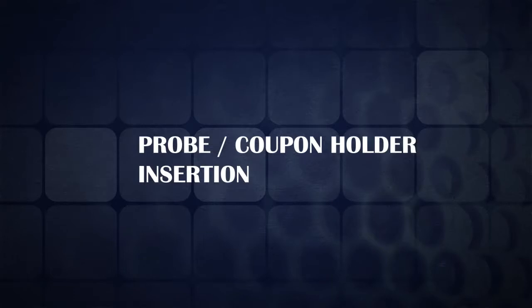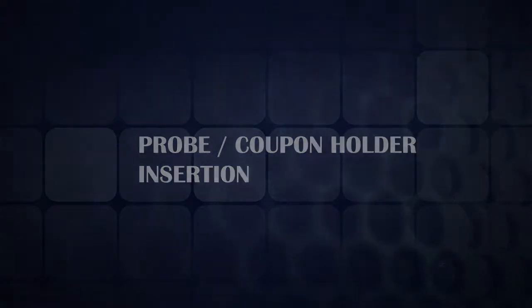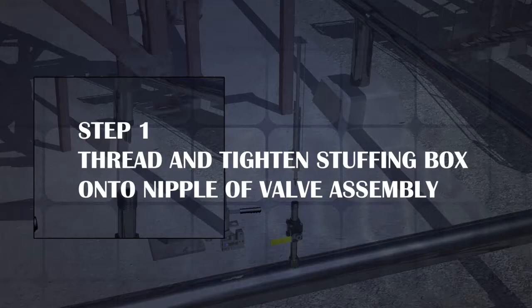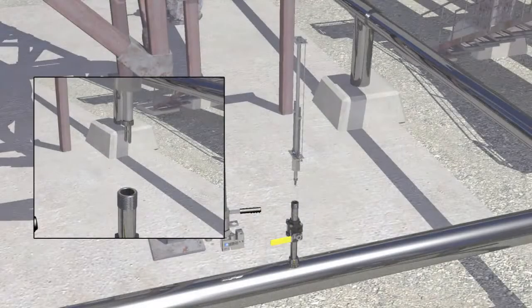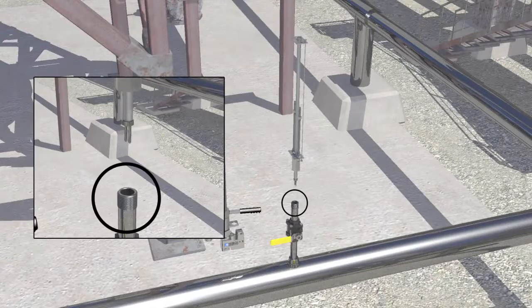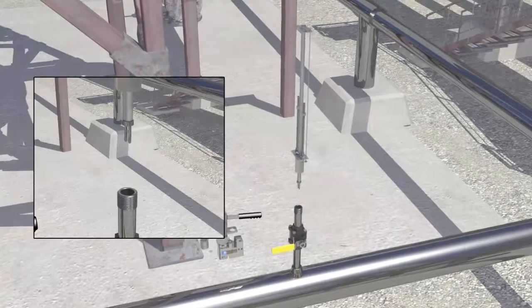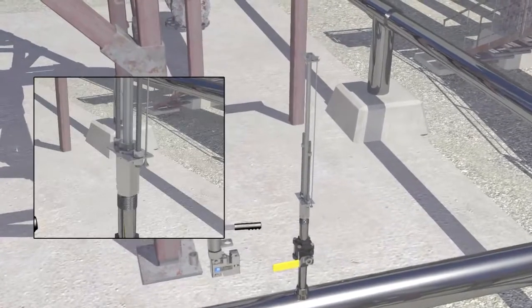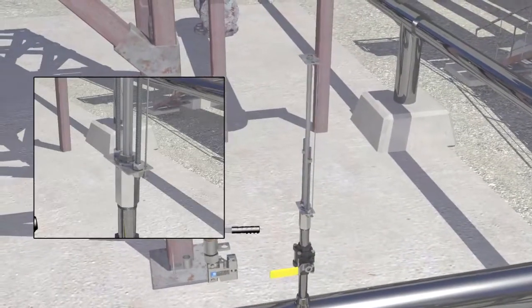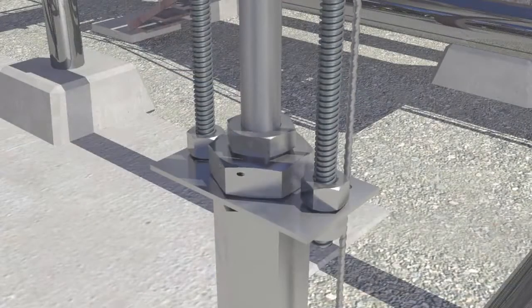Probe coupon holder insertion. Step 1. Thread and tighten the stuffing box onto nipple of valve assembly. Apply thread sealing compound or PTFE tape to the threads of the outlet nipple. Mount the stuffing box assembly onto the access valve outlet nipple and tighten to 2 3/4 to 3 1/4 full turns past hand tight. Tighten the 1.5 inch hex stuffing nut hand tight.